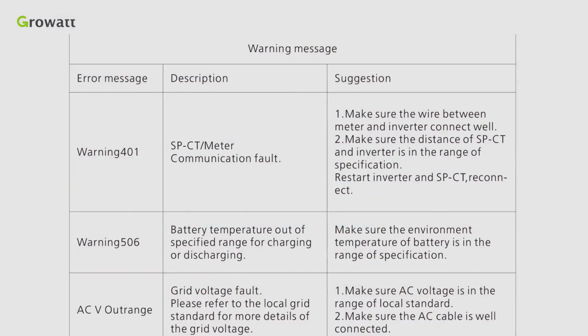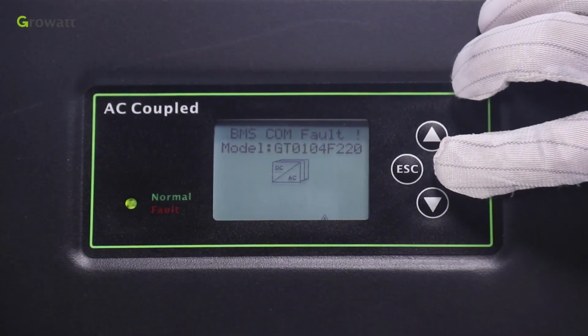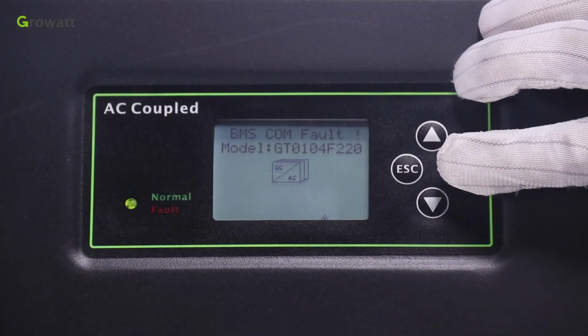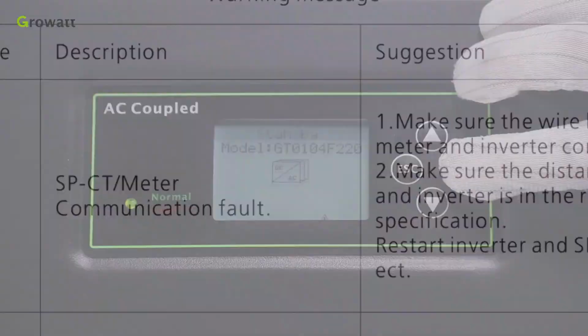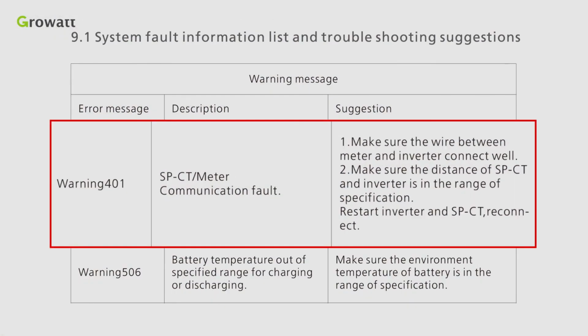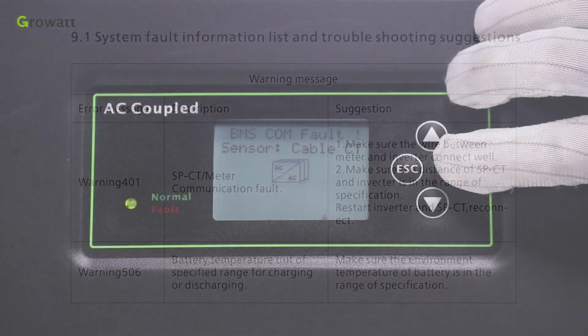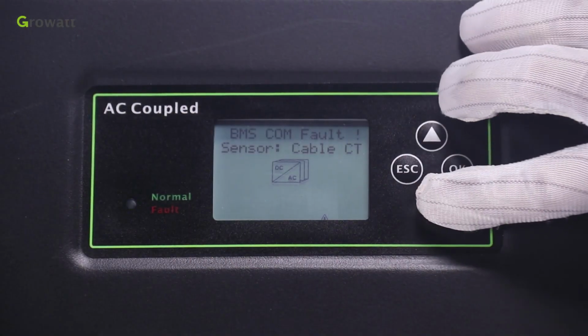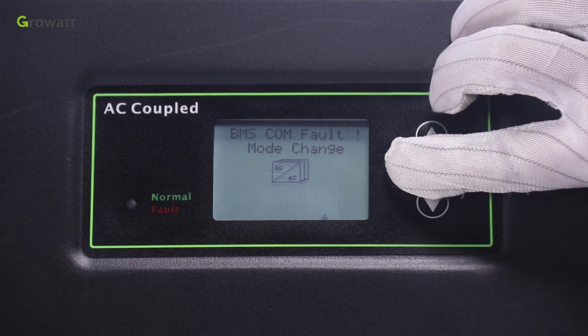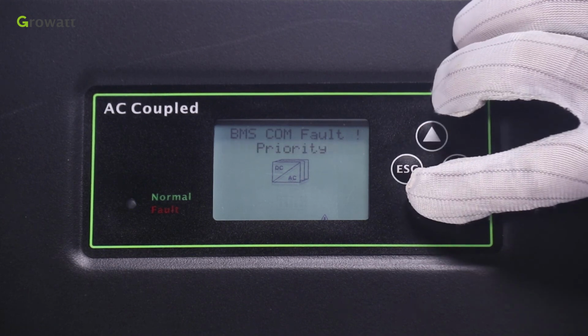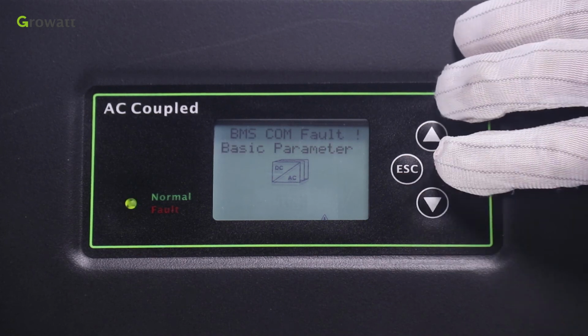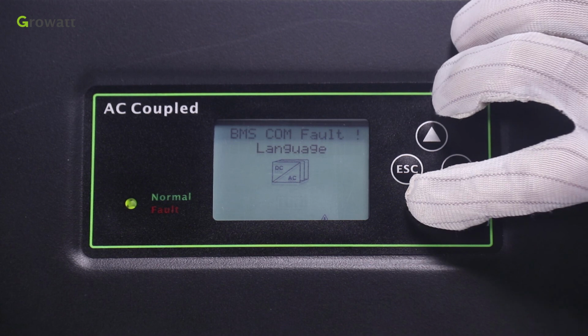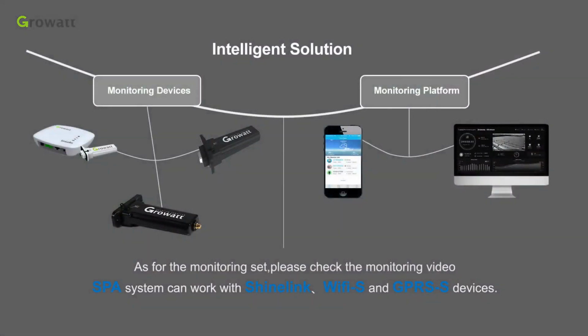There is a troubleshooting suggestion in our user manual. If the inverter gives fault information, you can refer to the list to repair it, such as the warning message 401. It means that the CT meter communication is wrong. You can check the wire connection and the distance between the devices. Then restart the machine. If there is something you cannot deal with, please contact Growatt Service Center. As for the monitoring setup, please check the monitoring video. SPA system can work with ShineLink, Wi-Fi S, and GPRS devices.